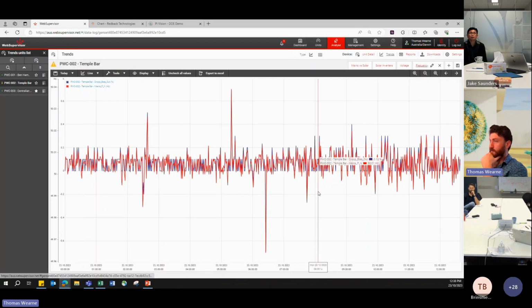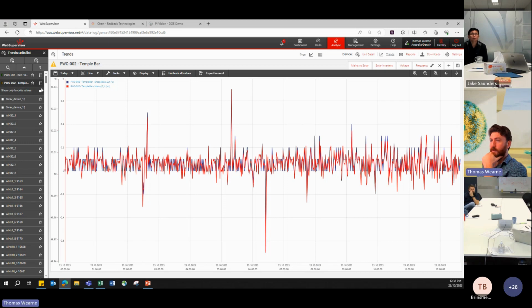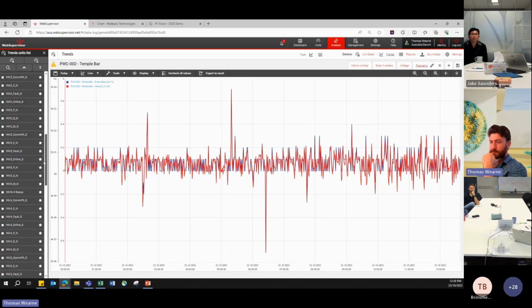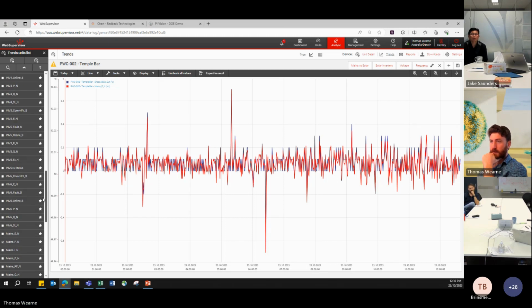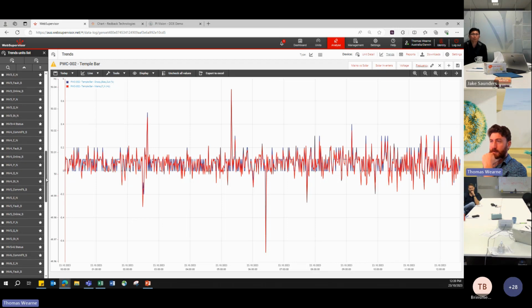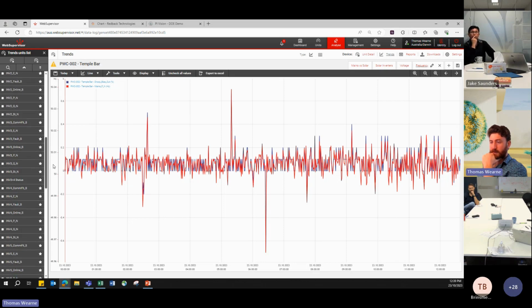So small changes in frequency result in small changes in the droop bias out, and we can also add in what the PV set point then becomes, which I'd normally look at to understand how you're actually changing the system based on frequency.